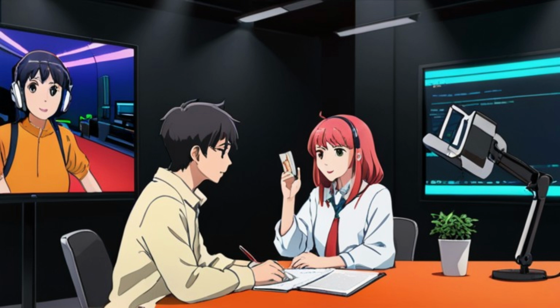Let's talk specifically about the pressure leak test. How is it conducted correctly and safely? This test provides valuable information about the overall system's leak tightness. It's imperative to use only dry nitrogen for pressurization, never oxygen or compressed air. The maximum test pressure should be 10 bar on both the high and low pressure sides. The procedure involves pressurizing the system with dry nitrogen, closing the regulator, and observing if there's a pressure drop on the pressure gauges, indicating a leak.